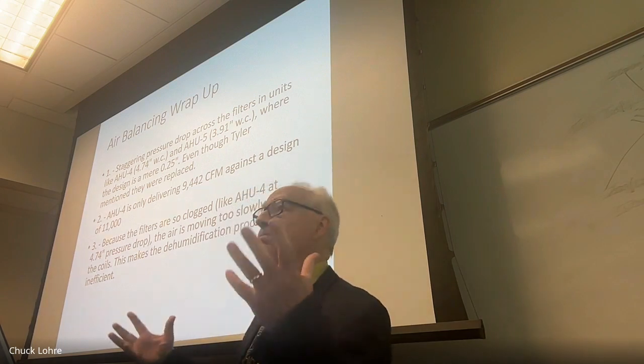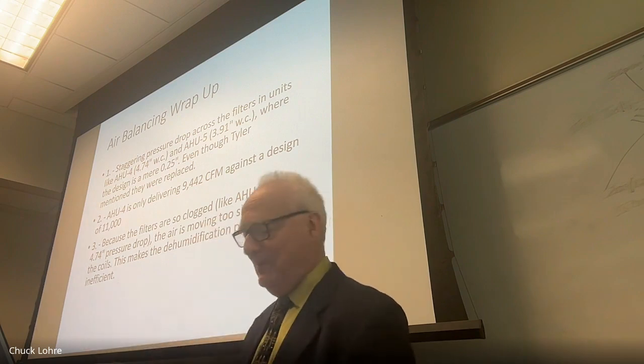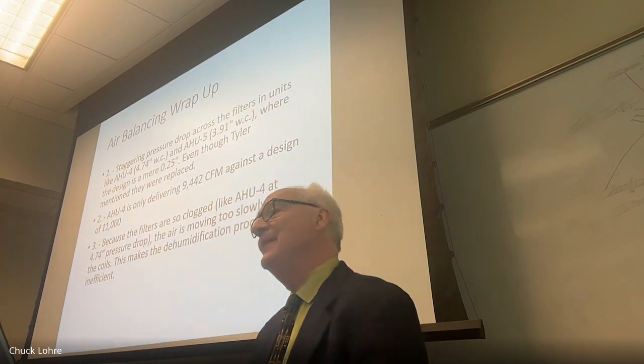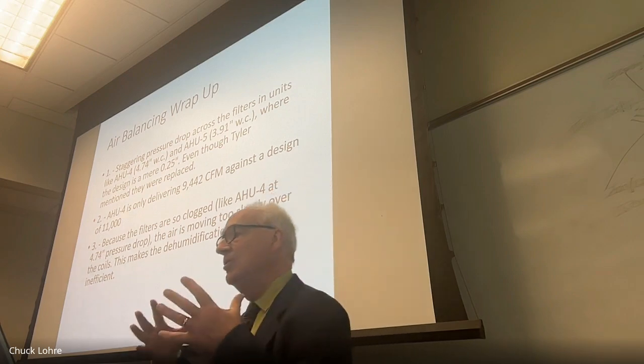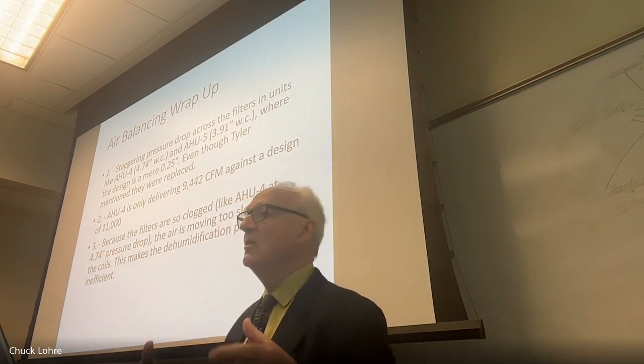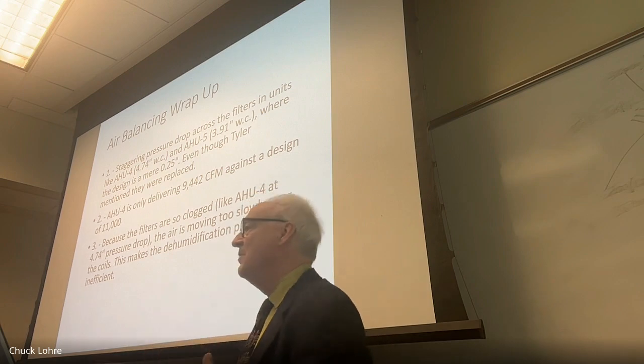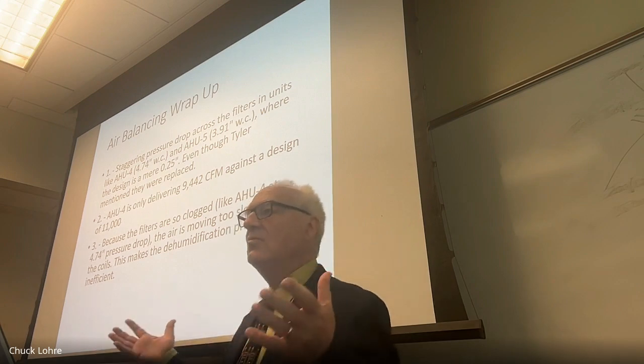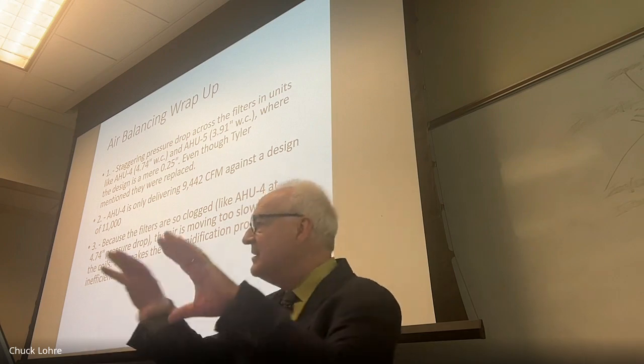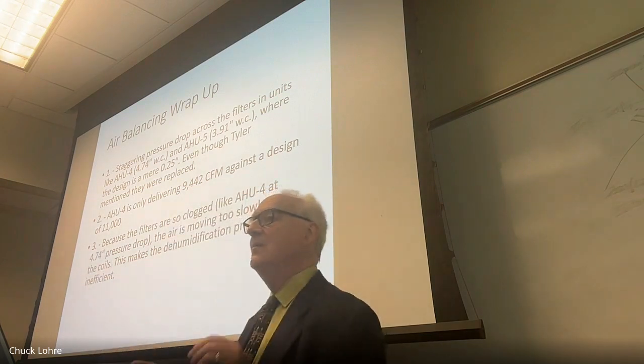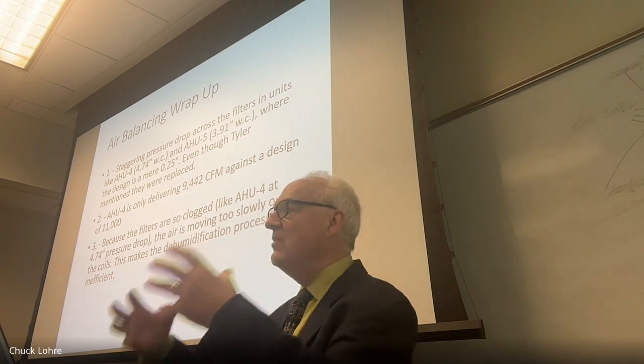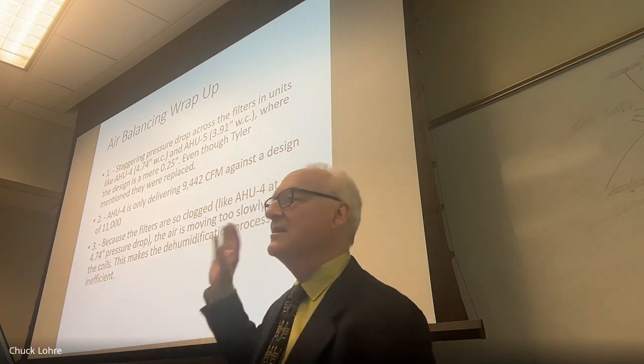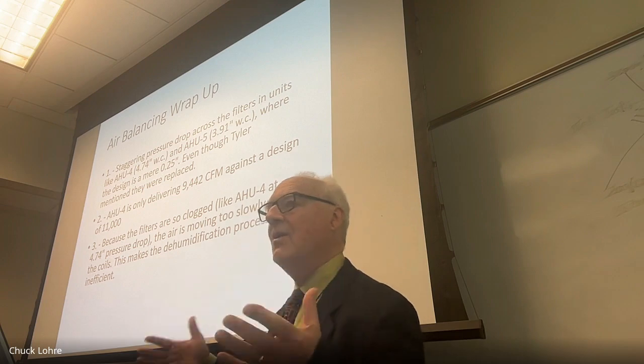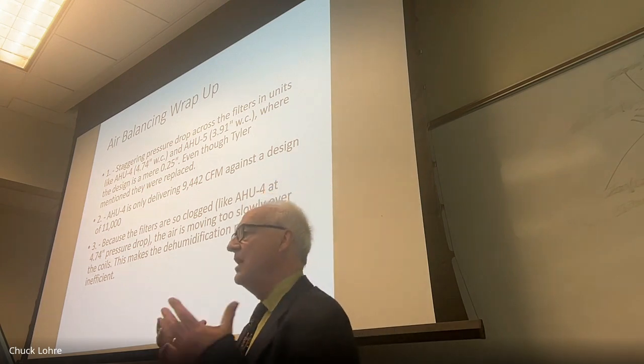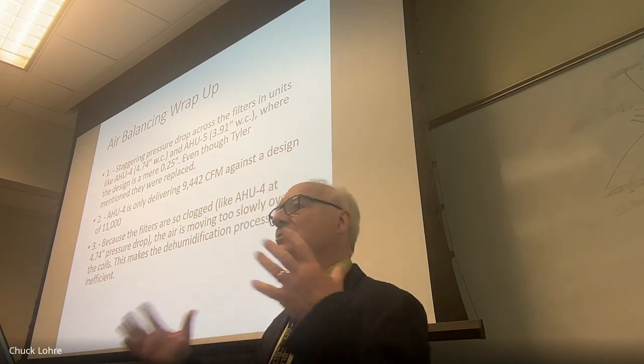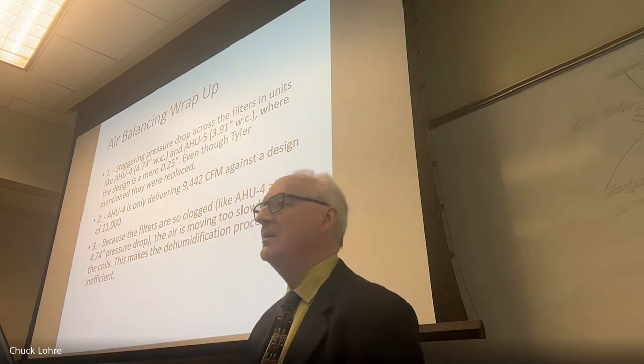It's amazing, this is a real detective story about the building. We're lucky to have the original contractor who worked on the CAC stay on as the building manager for 20 years - he did a great job maintaining that temperature and humidity. But there are some really serious fundamental problems with the way this HVAC system works if it's running at an EUI of 250. So we're trying to figure out how we can change this system so that it's more efficient.